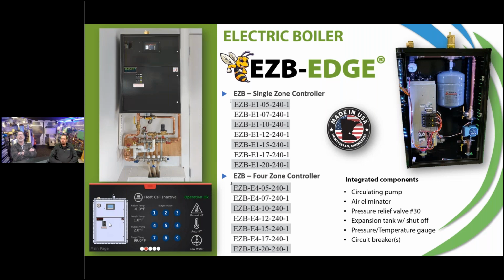Two things to point out: there's no combi per se, but can we do domestic hot water? Yes. Indirect storage? Yes. We do have an onboard circulator, and this doesn't necessarily need to be primary-secondary, but it can be. Like any appliance, we're worried about the flow through the vessel, so that's what we're taking care of—but that circulator can handle the house, the zones, the radiant, whatever the design calls for.